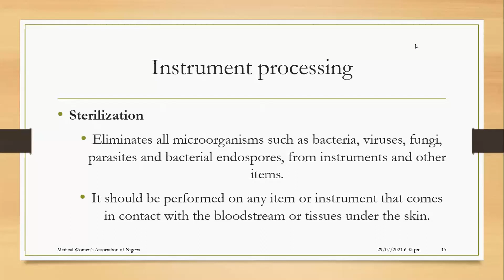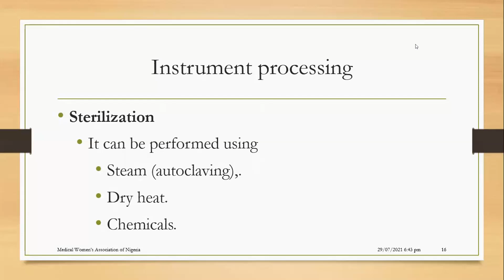Ideally, sterilization is the most recommended procedure. However, when you don't have sterilization, you can do high-level disinfection, which I will highlight later. For sterilization, you can do steam sterilization, which is autoclaving, dry heat, and chemicals. What we usually have available is either autoclaving or chemicals, and the chemicals are readily available in most cases. Not many centers have facilities for autoclaving, and it takes time and has more protocols involved. So chemical sterilization is usually what we do in most cases.